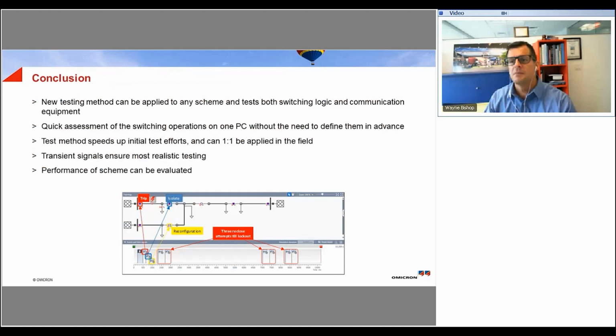And these tests can not only be used in the lab, but also be replicated out in the field via the GPS synchronization of remote test sets. As mentioned previously, instead of the steady state signals that are typically used, we can now use transient signals to ensure realistic faults. From all of that combined, we can make sure that the performance of the scheme is correct, and we can give it a thumbs up before putting it into operation. With that, I think I can take some questions.